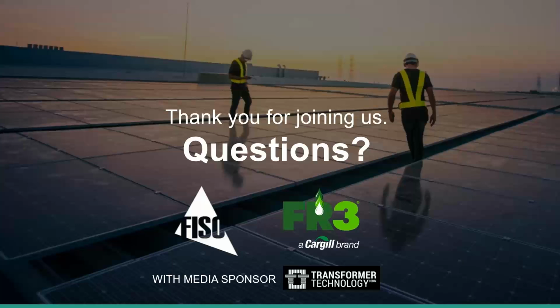So he specified the fiber optics to do design verification, and if there was some gap between reality and calculation, the transformer manufacturer had to pay some penalty to the client. So at the end, the first lot of transformers had this discrepancy, but the next lot was, I would say, nearly perfect. So it was a benefit for the end customer to control what he's buying. So going back to your question, I don't have real numbers. We say sometimes, let's say, a discrepancy higher than 3 degrees Celsius is difficult to accept. But yeah, I hope I could answer it somehow.